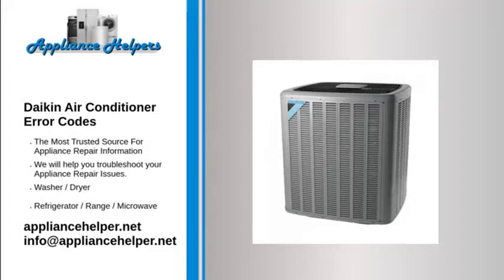Code A5. Problem: high pressure control and heating. Freeze up protection control and cooling. Clogged air filter of indoor unit and short circuit. Defect of indoor unit heat exchanger thermistor.